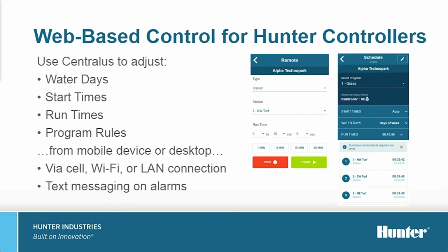And to go with that, we have now polished the web-based control for these Hunter controllers. With the Centralus web-based application, you have full control over water days, start times, run times, program rules from either a mobile device or a desktop. And communications can be established via cell phone, Wi-Fi, or LAN or Ethernet type connections. It will also text message managers and superintendents when alarms are detected in the field. So great feature for peace of mind because it's always on watch. It will text you when a problem is detected.